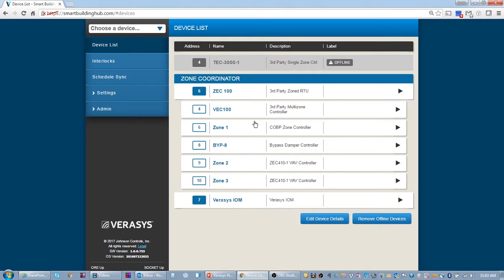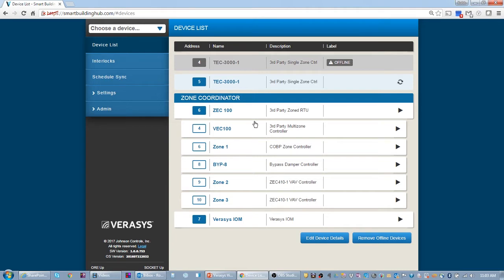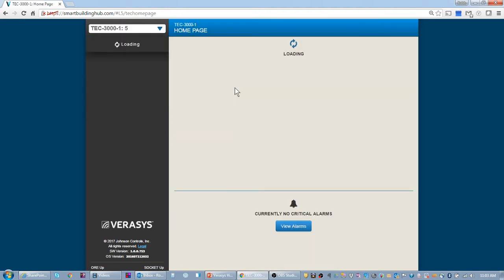For a normal building automation system, or I shouldn't say normal building automation system, but one that's got a supervisory controller, if you did something like this, you essentially would have to re-add all the points, or move the address manually through its configuration. You'd have to do some more work to make this come up and appear like what it once did.